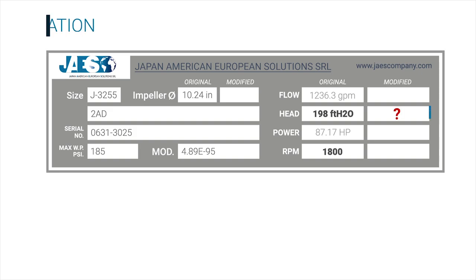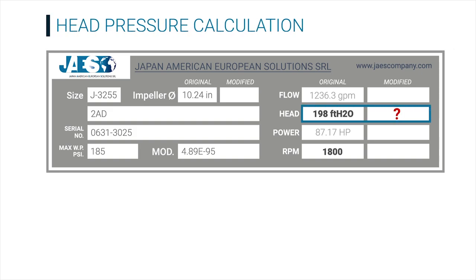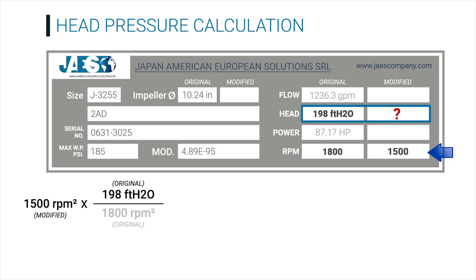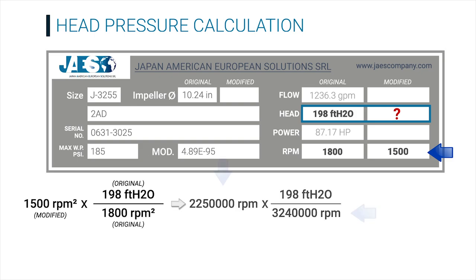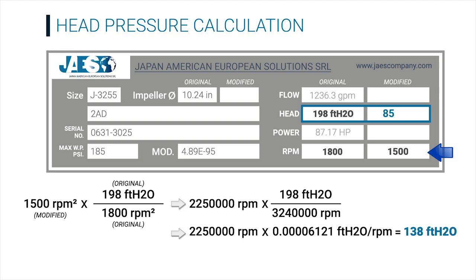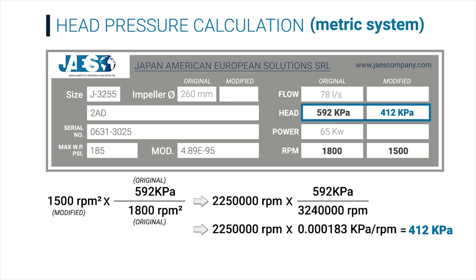If we want to find out the value of the new head pressure when we change the RPM from 1800 to 1500, we need to square the value of the modified RPM and multiply it by the division of the original head pressure — 198 feet of water — and the original RPM value, squared as well. Make sure to square both RPM values. The result is 138 feet of water. Using the metric system, the original head pressure value is in kPa and the resulting new head pressure is 412 kPa.